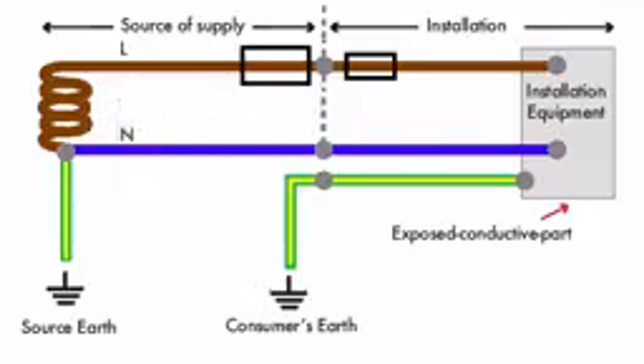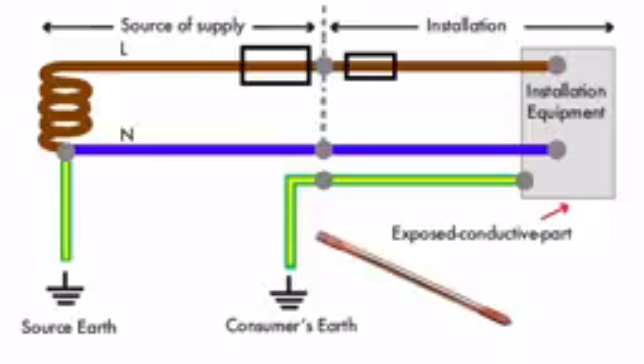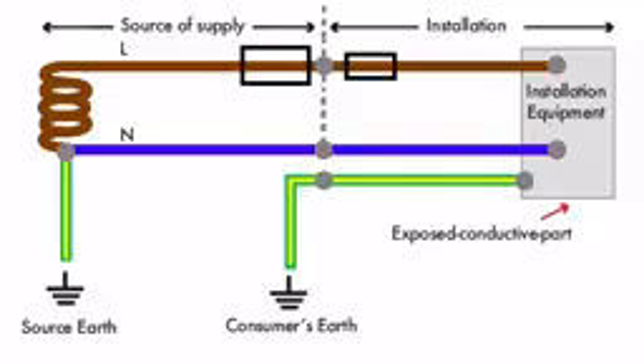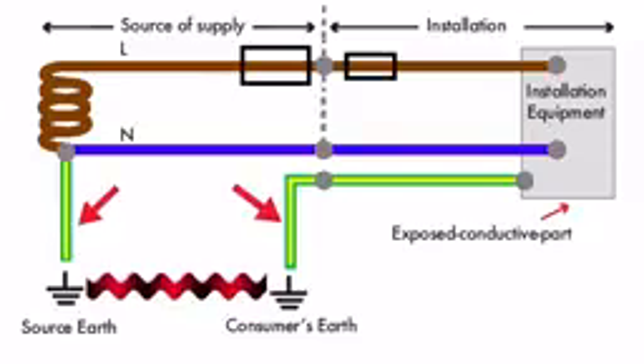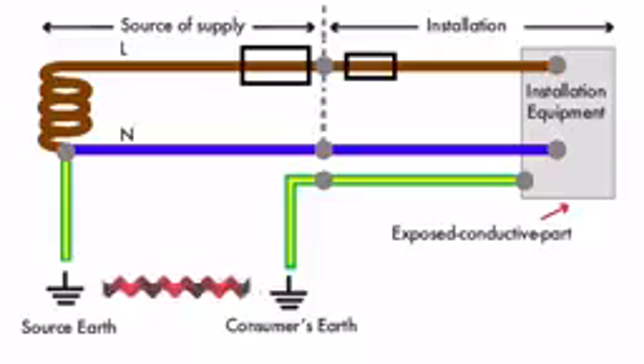It is the responsibility of the consumer within the installation to make their own connection to earth. This earth electrode usually comes in the form of an earth stake, but can come in other forms which we will discuss in the classroom. As the impedance between the consumer's earth electrode and the supply authority's connection to earth can be very high, installations must be additionally protected by an RCD in order to clear earth faults.